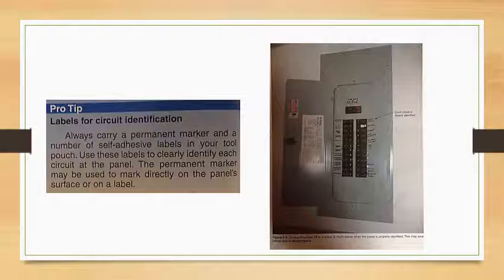Identification for safety. Major electrical equipment components and the disconnecting means of such devices should be clearly identified. Information on voltage, amperage, and equipment being controlled should be permanently marked on the disconnect means. Panel board circuit directories must be correctly labeled and located at the panel board. The intent of this rule is safety. Should a circuit or device need to be de-energized, the marking would allow for rapid action. See figure 7-2.